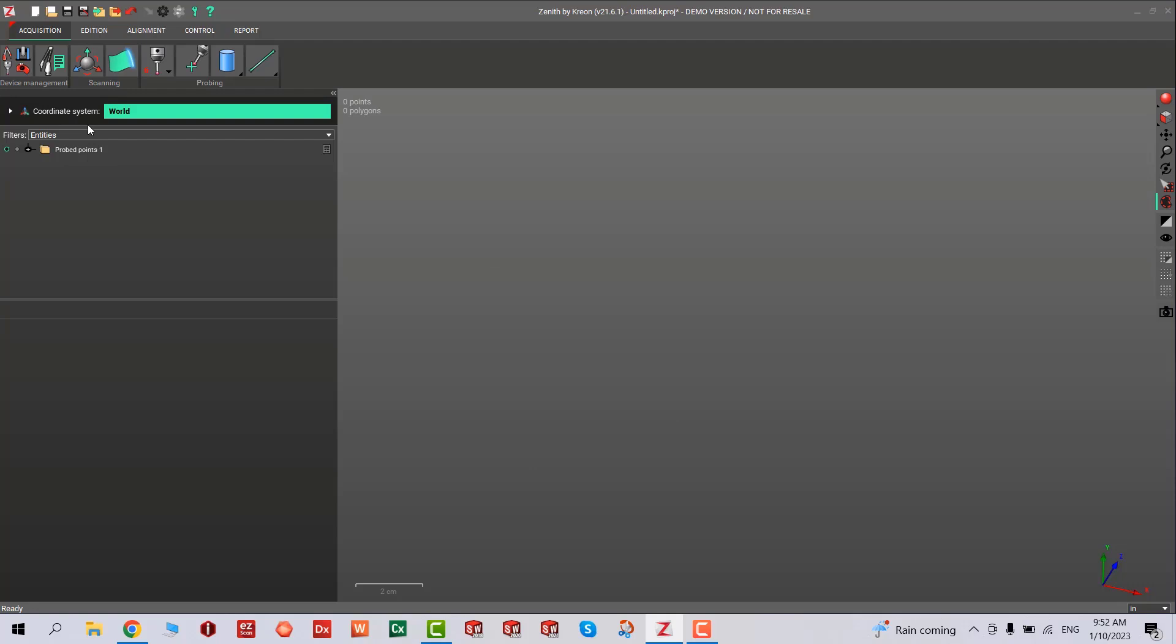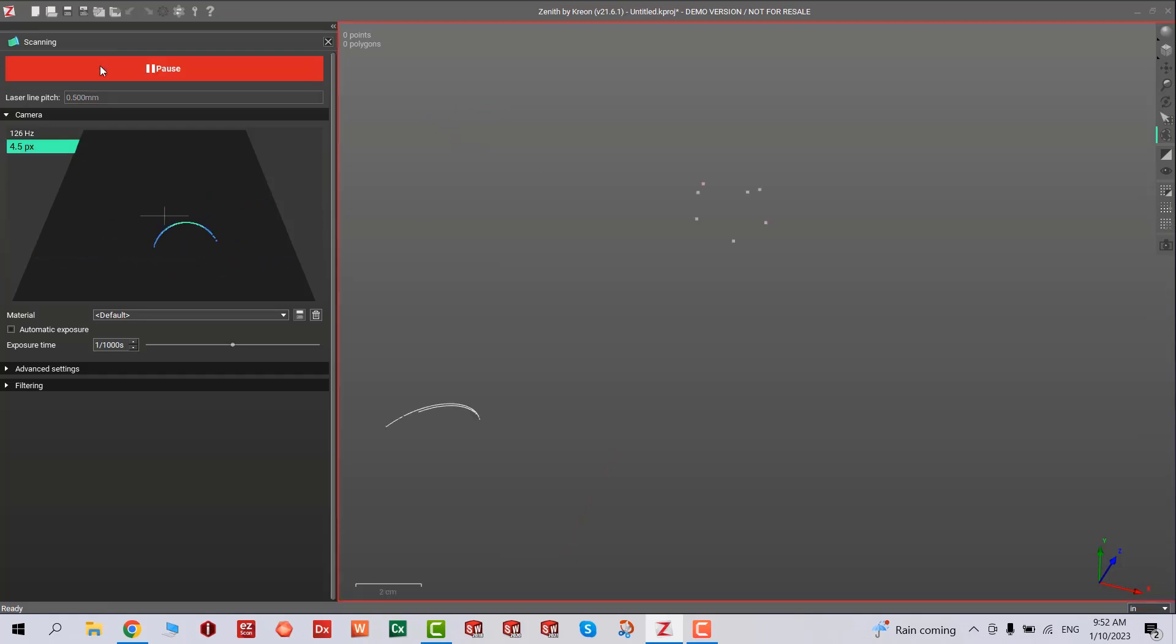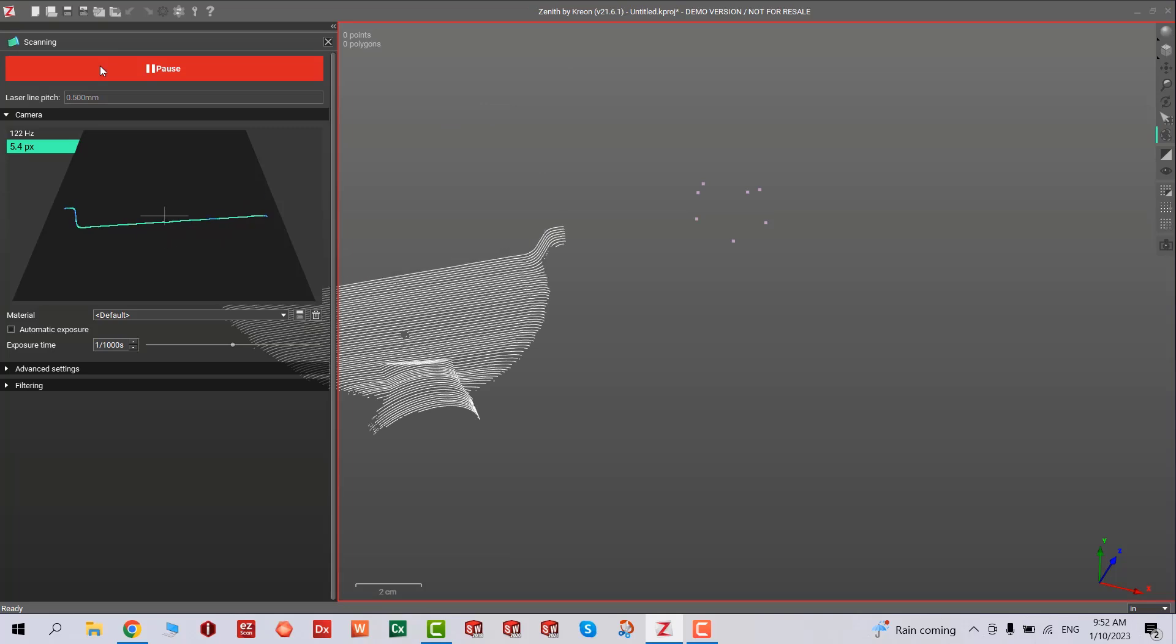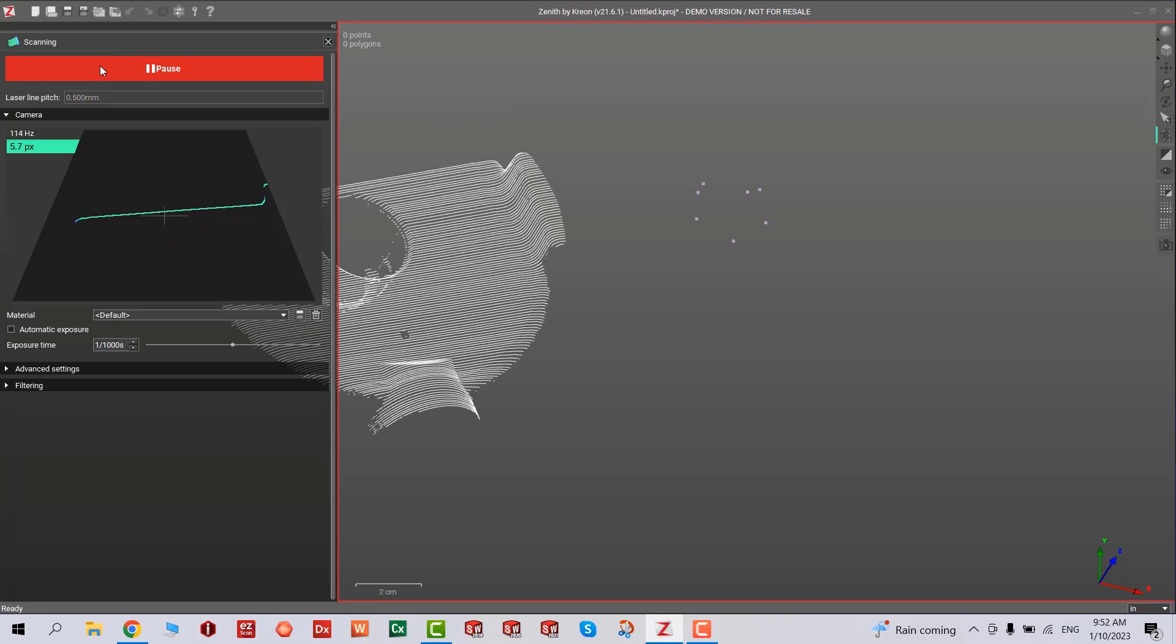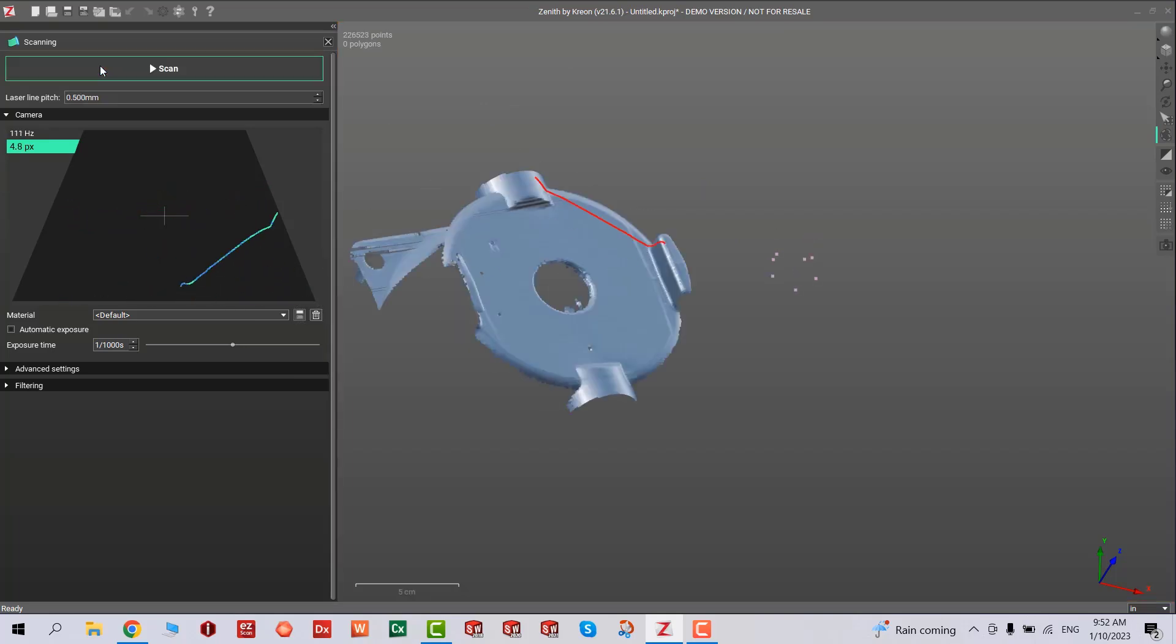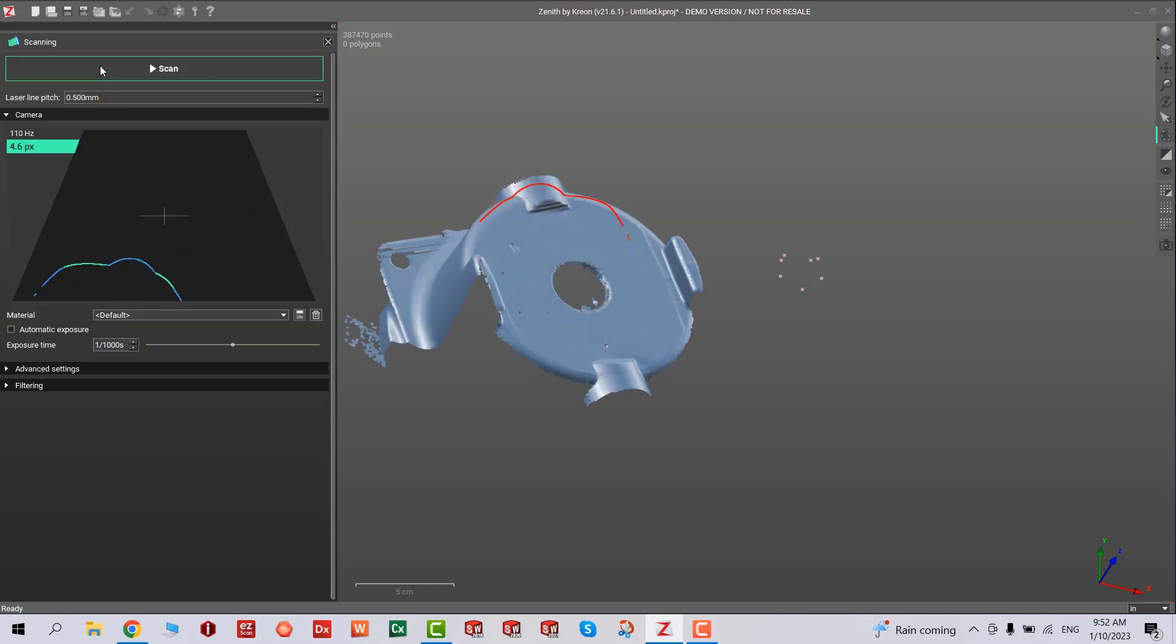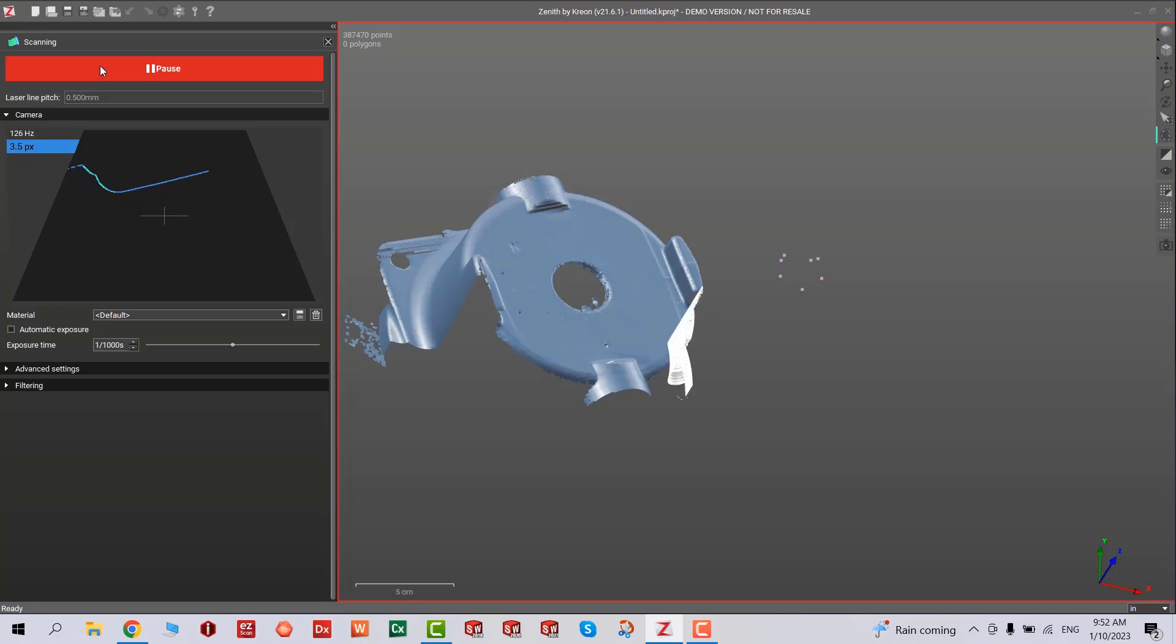I suggest you calibrate the probe and scanner before each use, just in case somebody bumped into it or maybe it's not in the correct position. If you remove the head assembly, make sure you attach it back and then recalibrate.